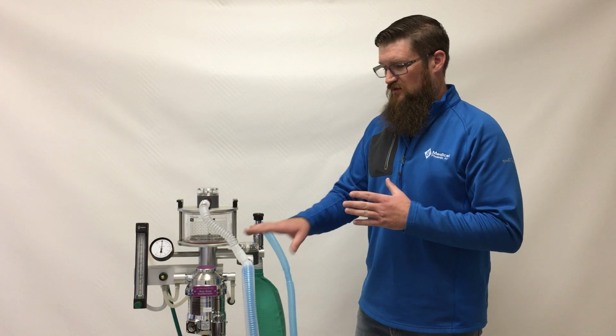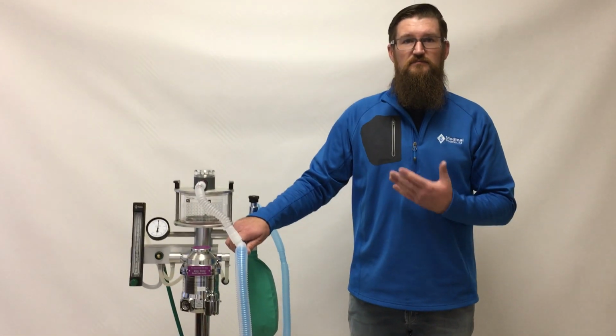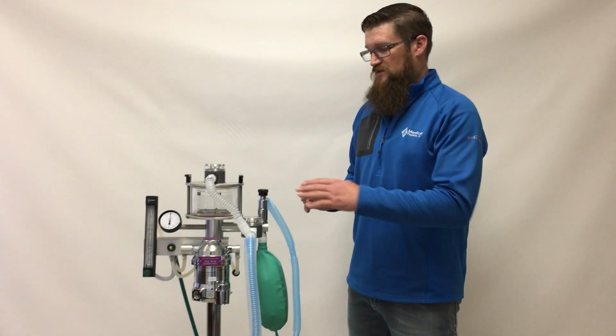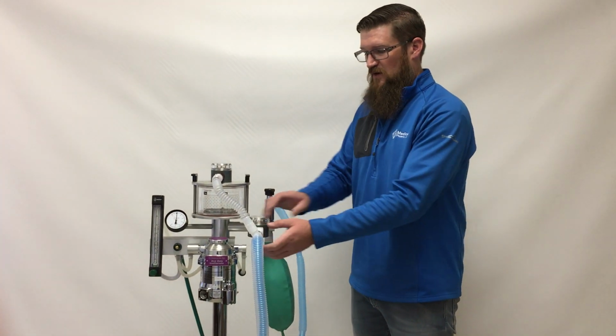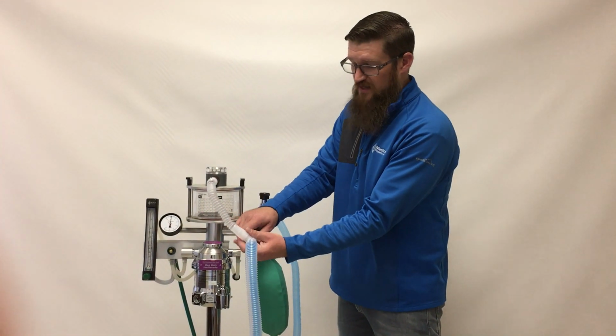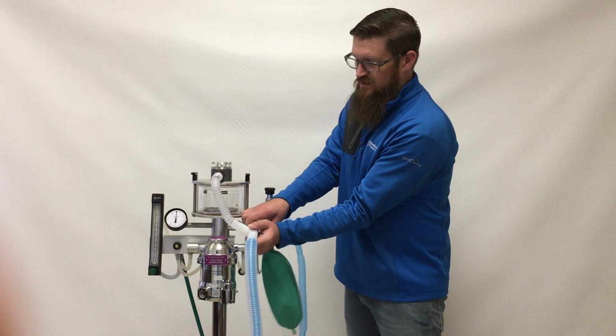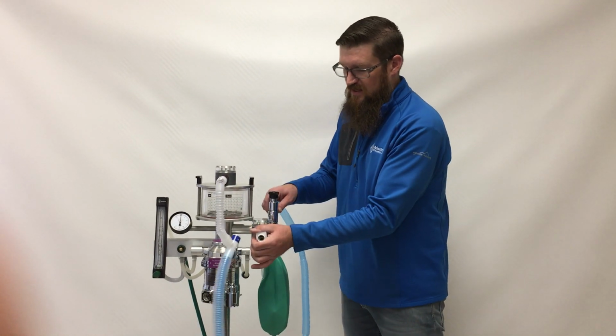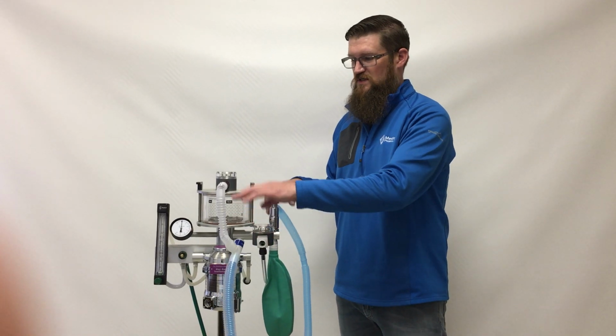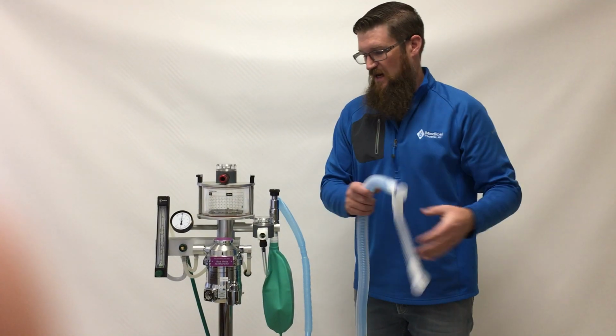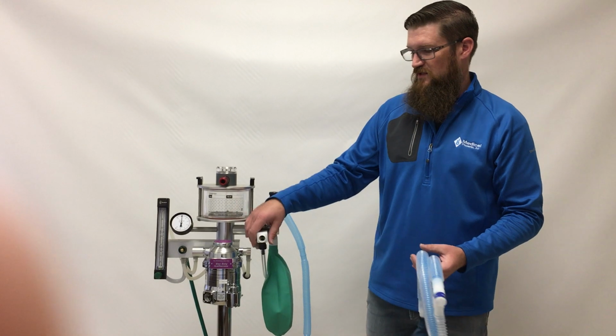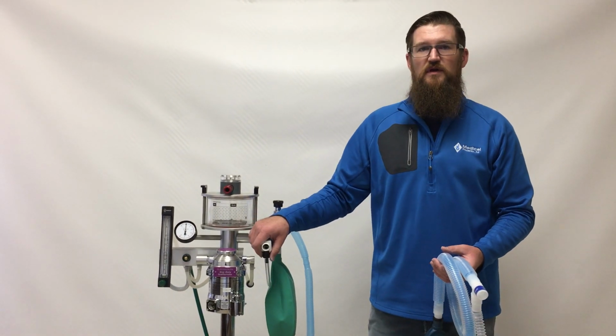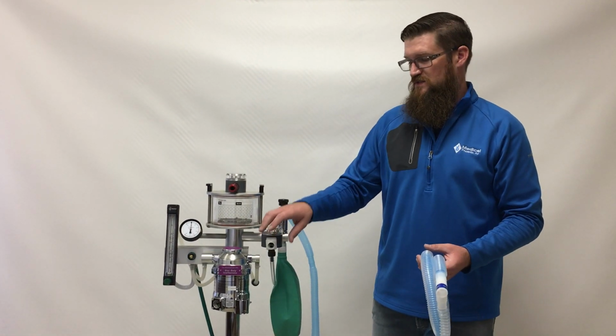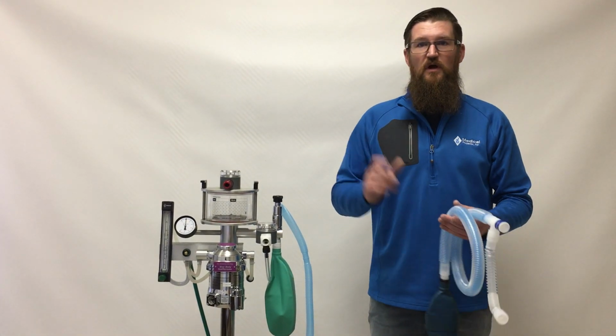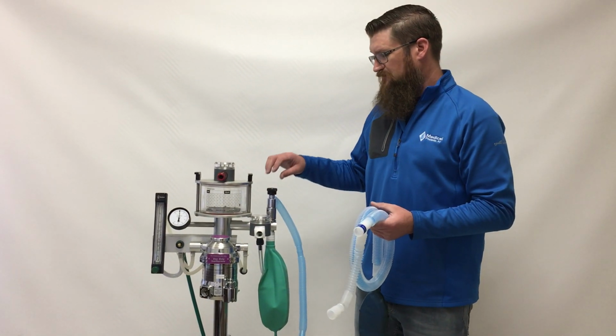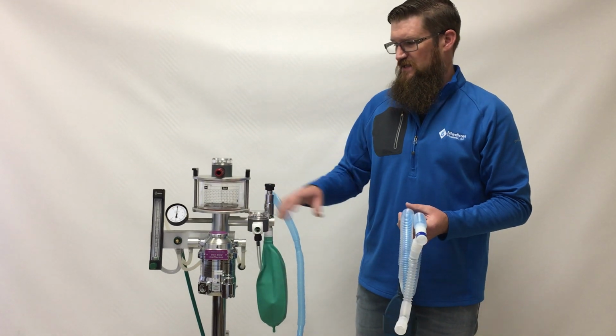The maintenance of the valve is virtually nothing, especially when it's connected on the inspiratory circuit, or inspiratory side of the circuit. If it's connected in the expiratory side, it's not a bad idea to let it sit. You can disconnect the circuit from it just to let it air out in case there's any moisture buildup. But if it's on the inspiratory side, you won't be building up any moisture in there, and it should stay just fine and operate fine for a very long time. But letting it air out is always a good idea.